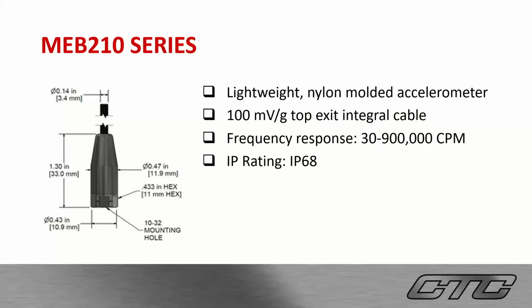Shown on the screen is the MEB 210 series. This is our lightweight nylon molded accelerometer with 100 millivolt per G top exit integral cabling. The frequency response for this is 30 to 900,000 CPM, and the IP rating for this is IP68.